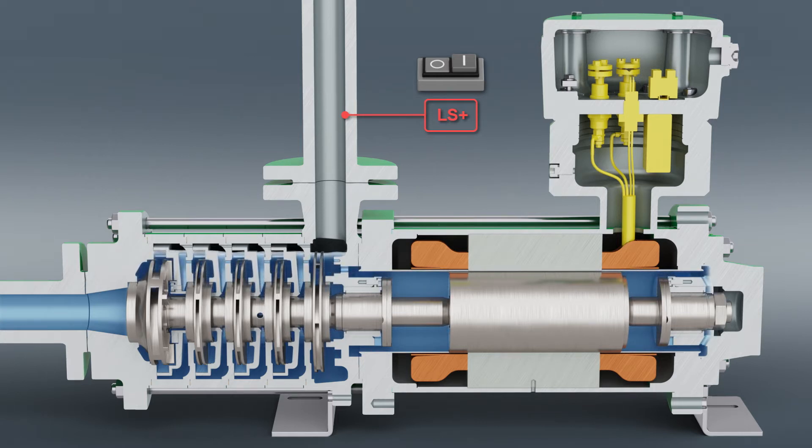During or shortly after filling, potential air pockets in the back of the motor and in the area of the impellers and bearings are vented out of the discharge nozzle. The Hermetic Multi-Stage Canned Motor Pump is self-venting.